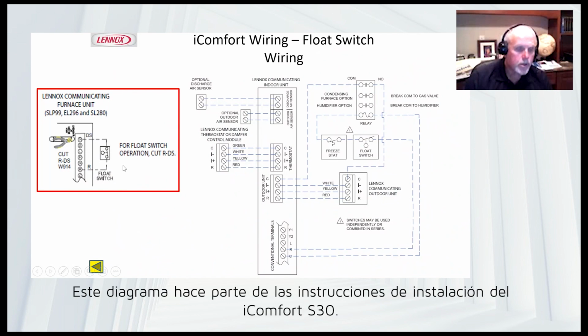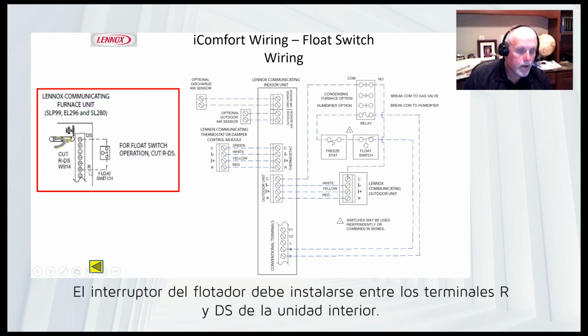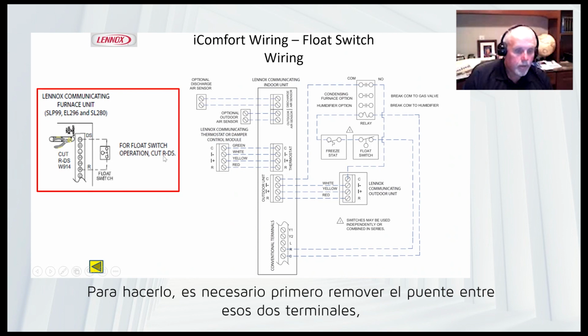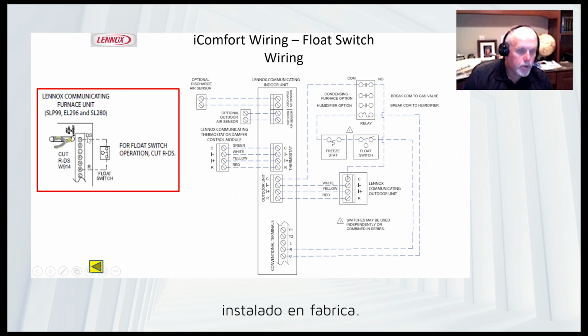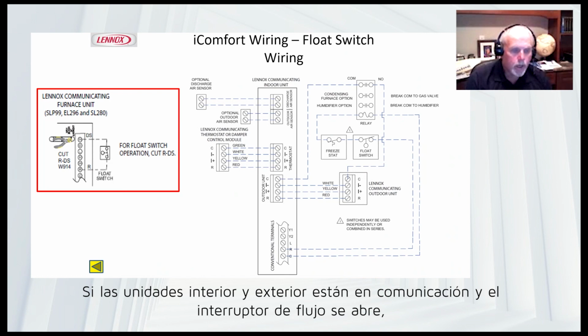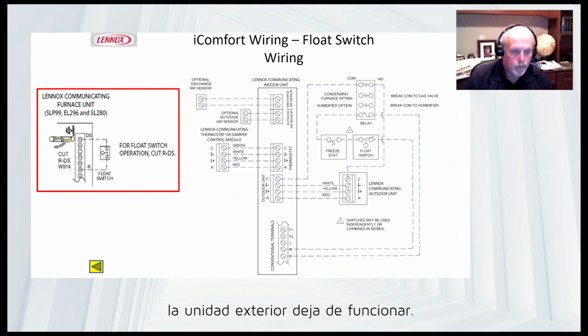Okay, now all this wiring is in the installation instruction for the S30. Okay, so you would wire it between R and DS on the conventional terminal strip of the indoor board, and you would clip the jumper from R to DS. Okay, there's a jumper right near the terminal strip, and you would clip that R to DS jumper and wire your float switch in like this. So if both your indoor and outdoor unit are communicating, if the float switch would open, that would shut down your outdoor unit.